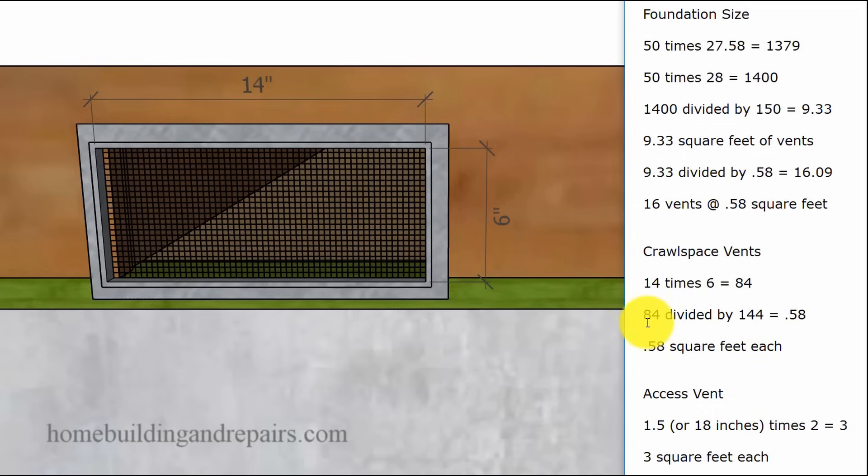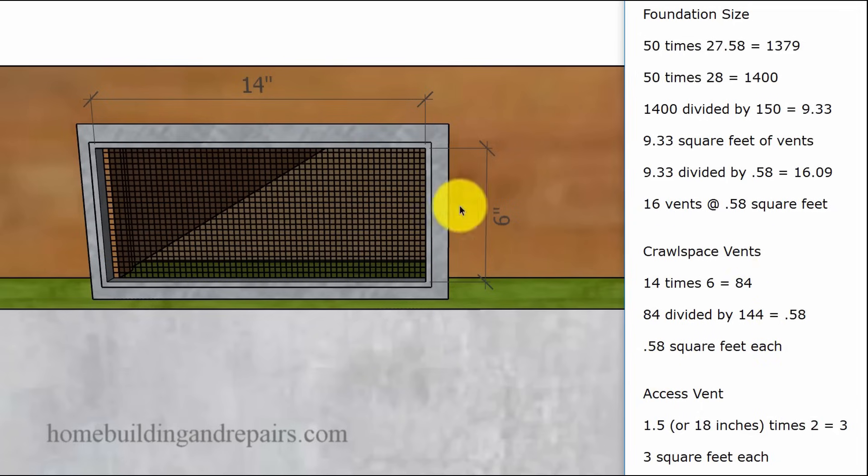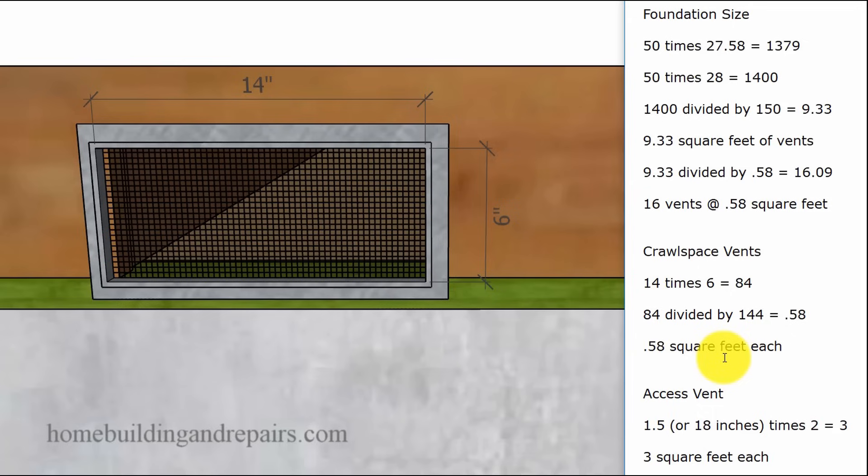If we divide 84 into 144, we're going to get 0.58. Each crawlspace vent is going to give us 0.58 of a square foot as a decimal, and of course 3 feet for the access vent.